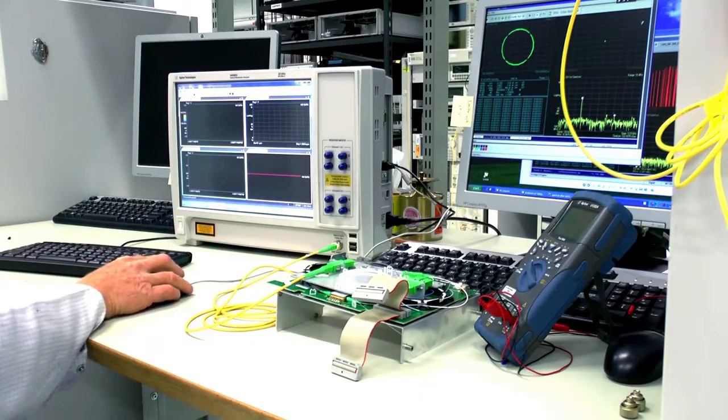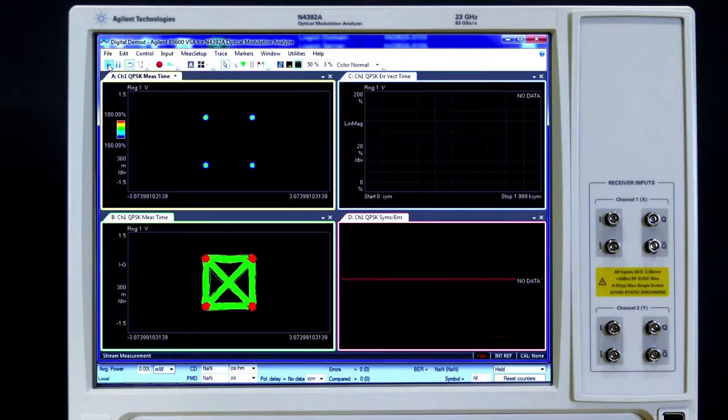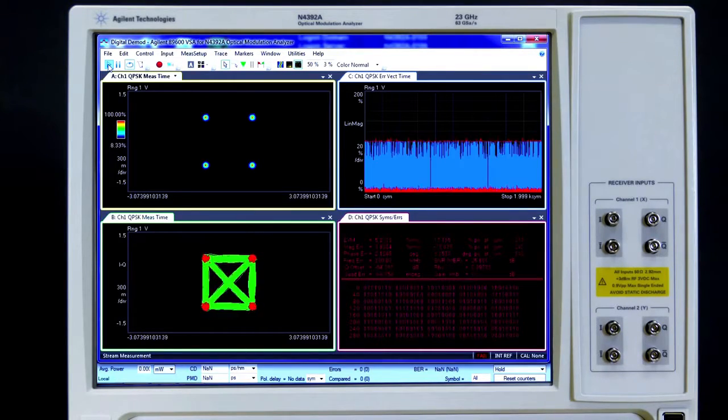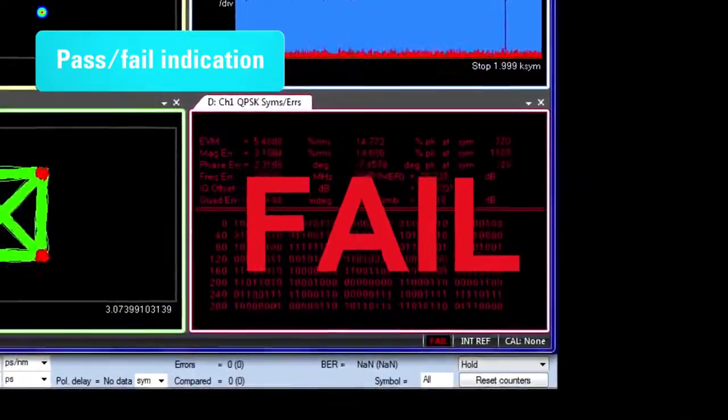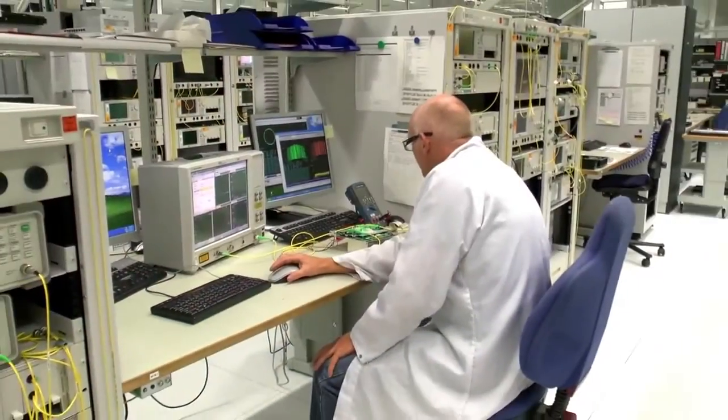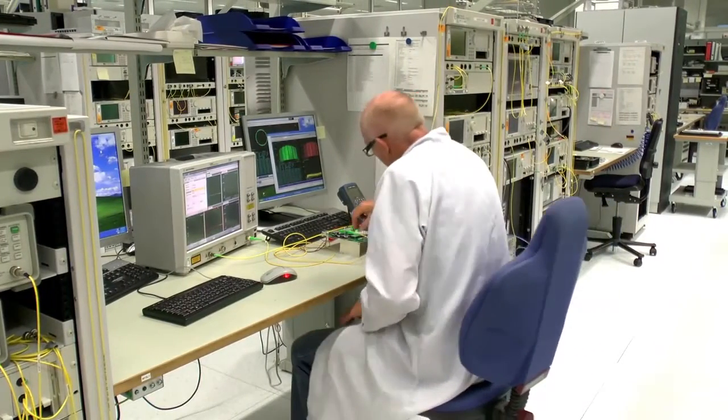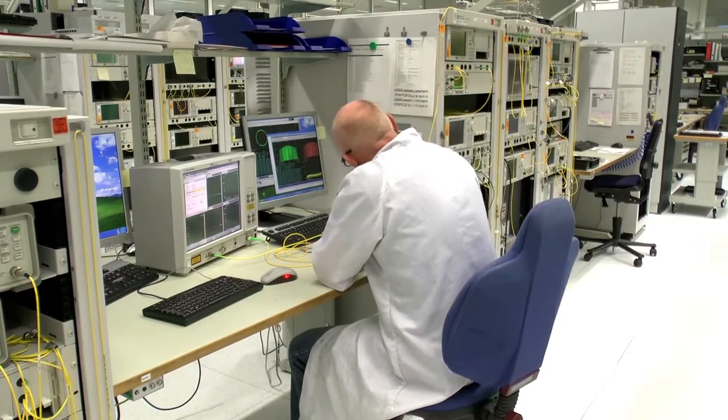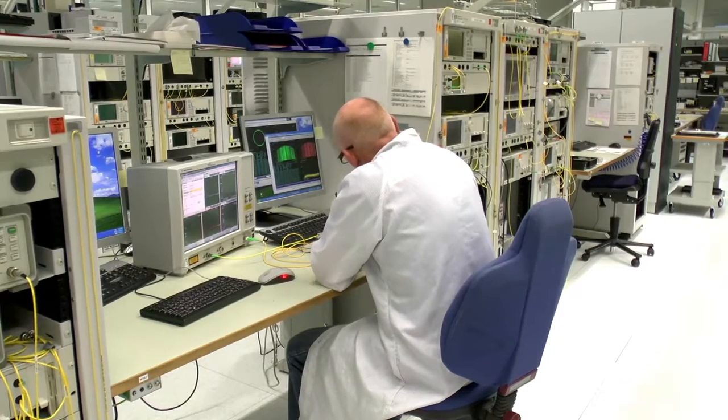It opens up possibilities for testing the signal quality of your devices during manufacturing. This could be in an automated environment for one-button pass-fail testing or for aligning the modulator. Of course, the N4392A has more than enough potential to go into action for debug if that is necessary.